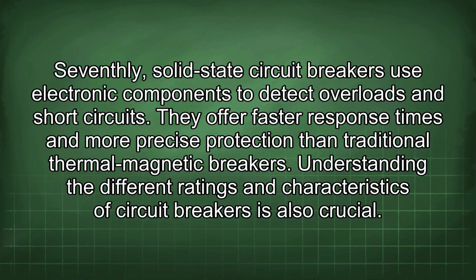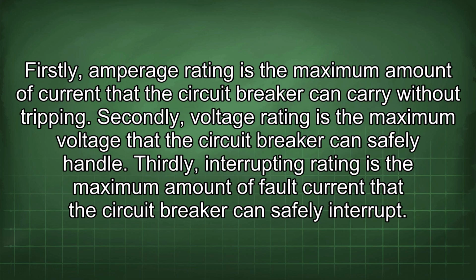Understanding the different ratings and characteristics of circuit breakers is also crucial. Firstly, amperage rating is the maximum amount of current that the circuit breaker can carry without tripping. Secondly, voltage rating is the maximum voltage that the circuit breaker can safely handle. Thirdly, interrupting rating is the maximum amount of fault current that the circuit breaker can safely interrupt.